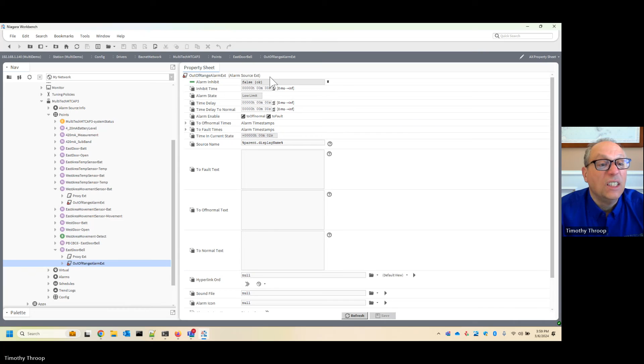I'm going to create what's called an out of range alarm — or rather, an off normal alarm. The message I want to send out when this happens is 'doorbell pressed.' Save that. Going back to my points, you can see it's already showing as 1.